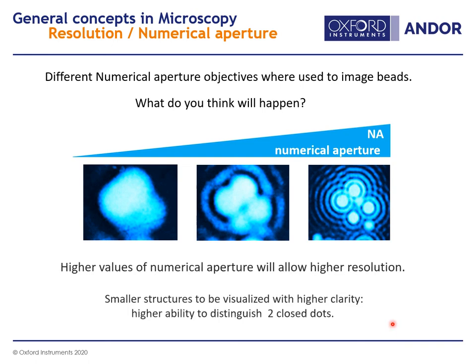Here I have an image of beads that were imaged at different numerical apertures. As you increase the numerical aperture, you widen the angle of light captured by the objective and therefore increase the resolving power. We go from a blob where we don't know what's there, to finding out that there are four beads in that blob. Higher values of numerical aperture allow higher resolution, and smaller structures become visible with higher quality. Resolution is the ability to distinguish two close dots as separated.